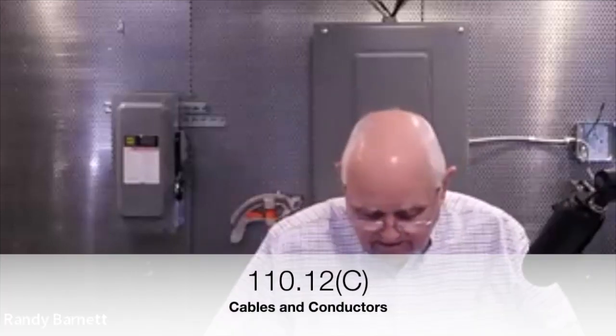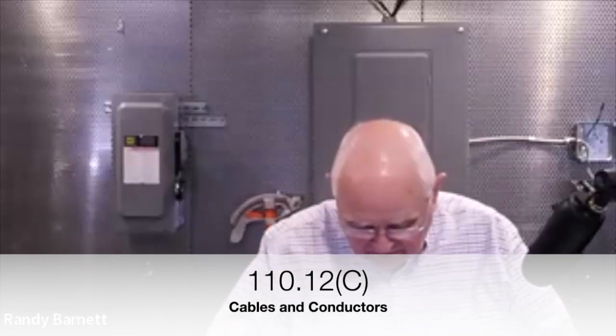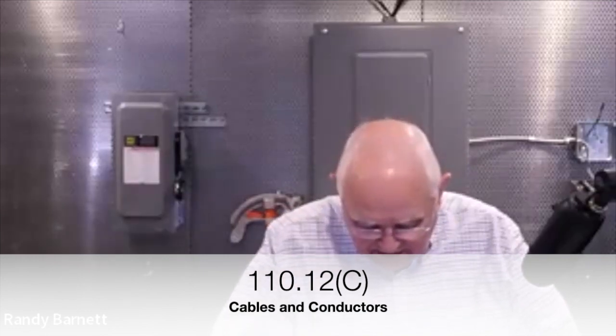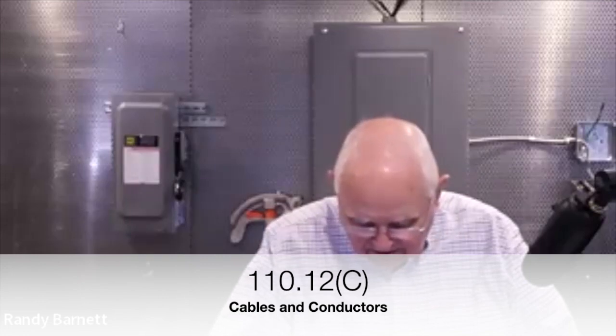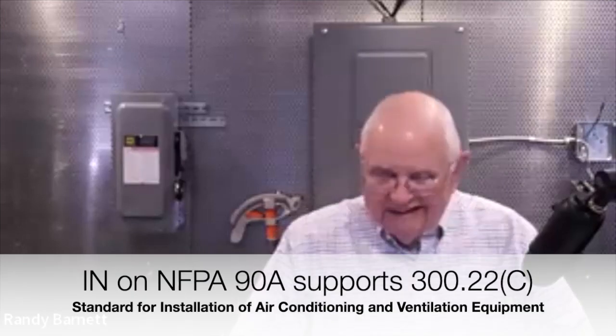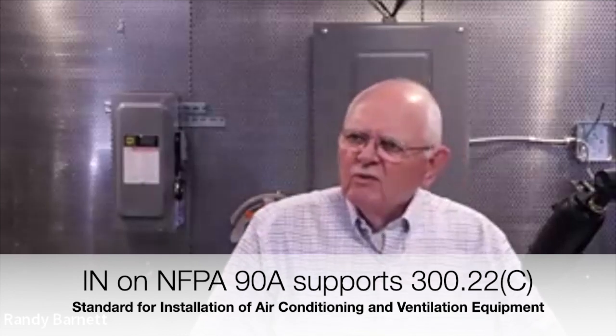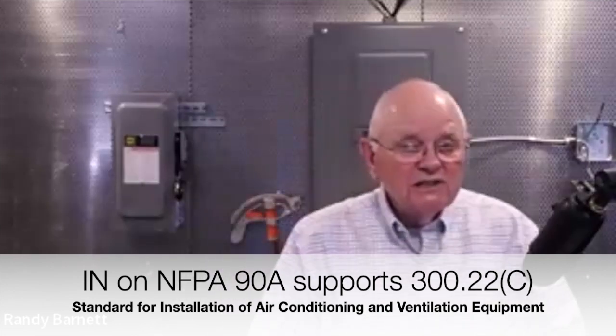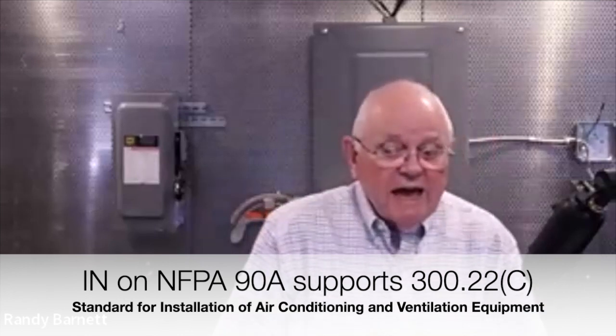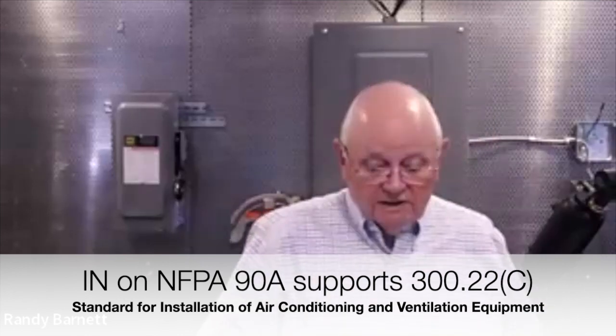So this is cables and conductors, 110.12(C). Cables and conductors installed or exposed on the surface of ceilings and sidewalls shall be supported by the building structure in such a manner that the cables and conductors will not be damaged by normal building use. The reference in this first informational note is going to take us to NFPA 90A, which is the standard for installations of air conditioning and ventilation equipment. And really, if you think about it, the information in NFPA 90A is going to help us support 300.22(C).